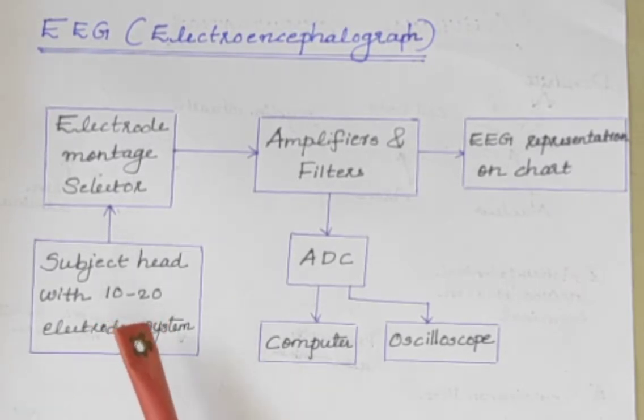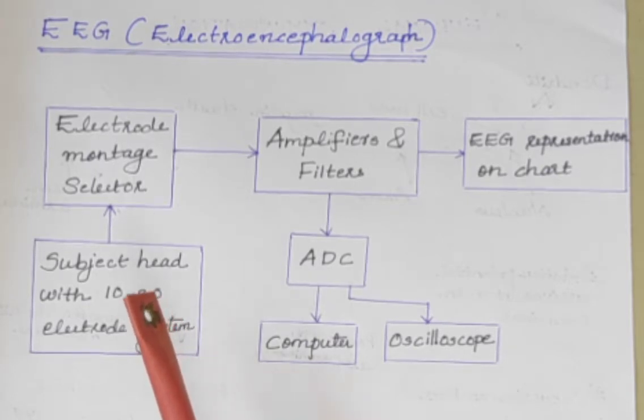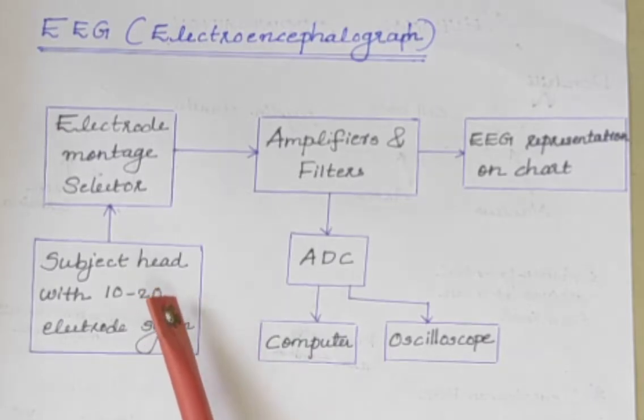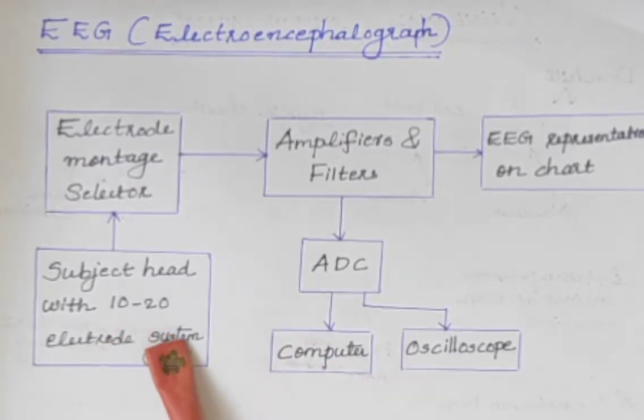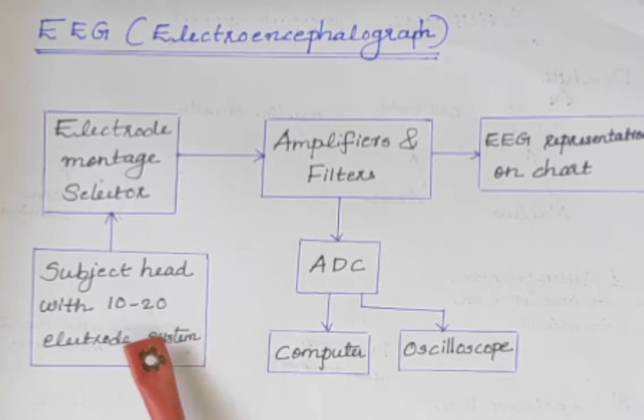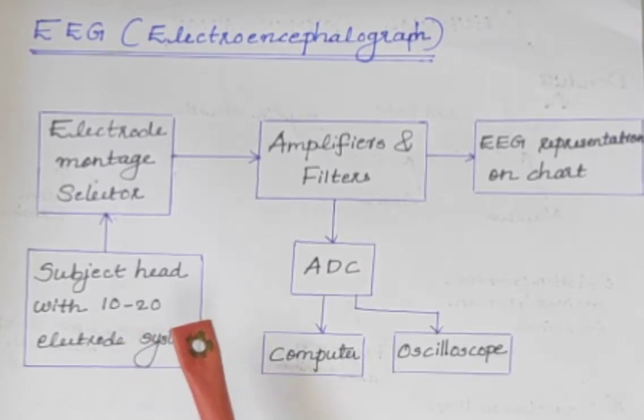EEG electrodes are smaller than ECG electrodes. EEG electrodes are arranged on the scalp according to a standard known as the 10-20 system. The numbers 10 and 20 refer to the fact that the distance between adjacent electrodes are either 10% or 20% of the total front-back or right-left distance of the skull.